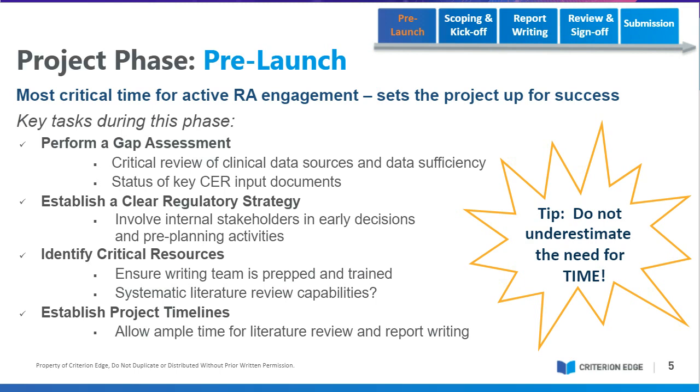Do you have them? Are you clear about what the MDR and IVDR demand in a CER for that documentation and that methodology? Because the thing I always say about this is that systematic literature review is how you identify published data on your device for the most part, or on your competitor device, how you establish your acceptance criteria and state of the art. So if that methodology is not crystal clear to your notified body reviewer every step of the way, and to them that means reproducible, if they could look at what you wrote in the CER as far as your documentation of your methodology, and could do it themselves and come up with virtually the same results, that's their bar.